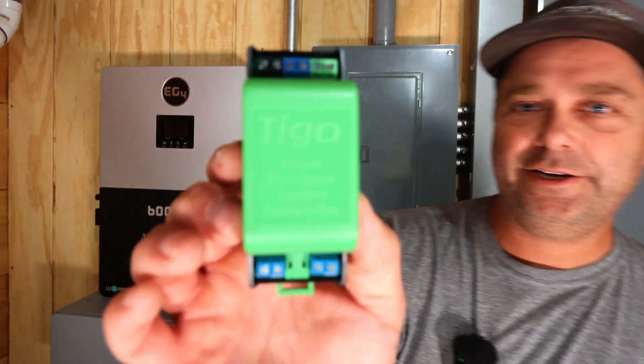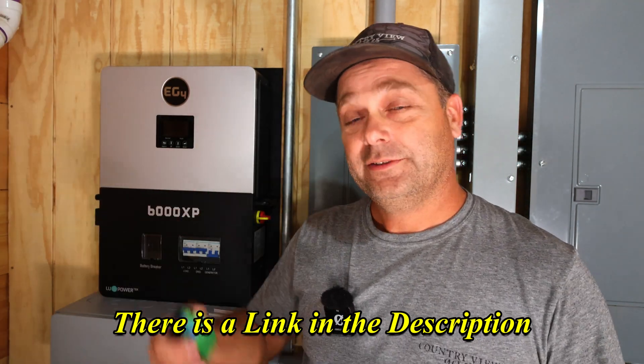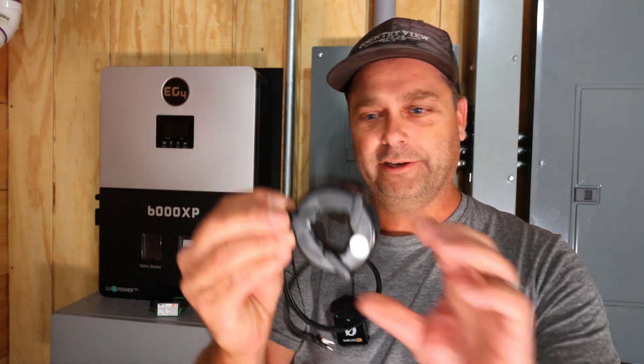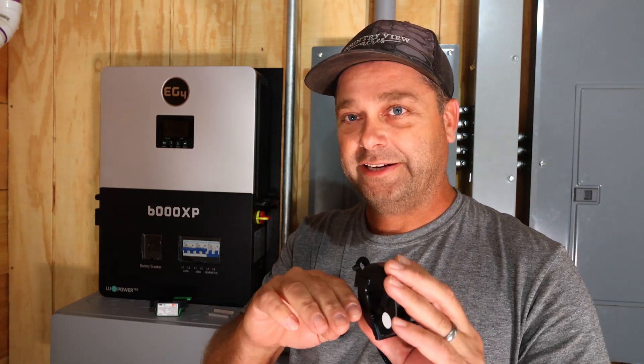This is the Tigo rapid shutdown transmitter. It transmits a signal out to the shutdown modules installed on our solar panels and tells them it's okay to turn on. Once this signal stops, the solar panels will actually shut down and be at a safe voltage. It sends that signal through the solar panel wiring — you run one of the solar panel wires through this core, which induces a signal onto the wiring, and that's how it communicates out to the module on your solar panel.